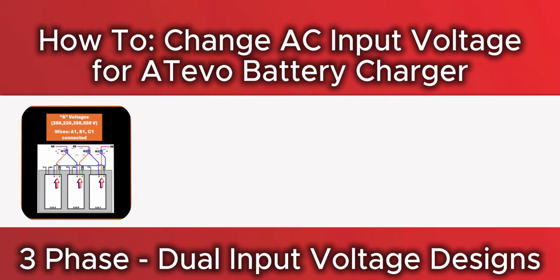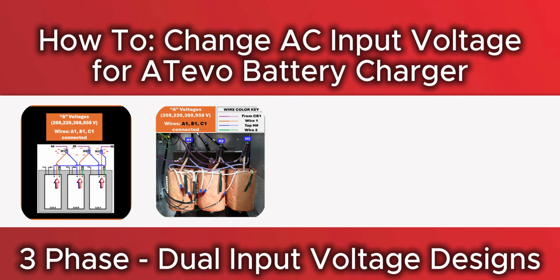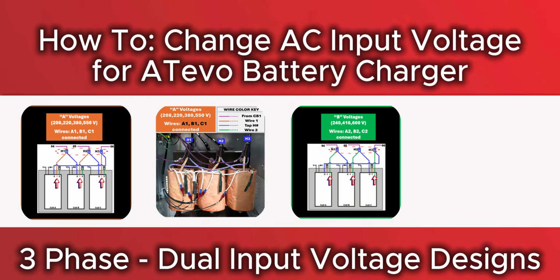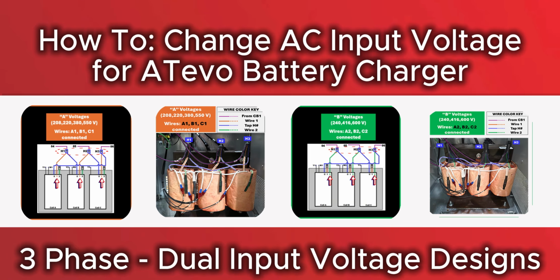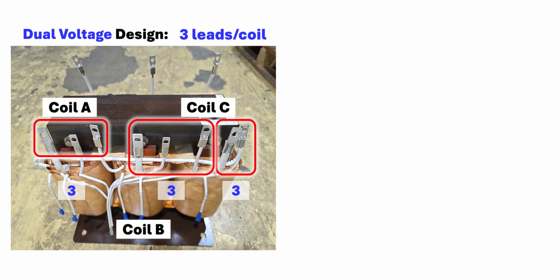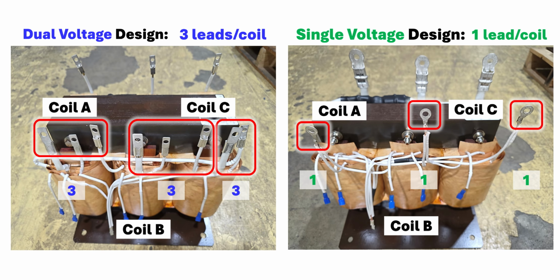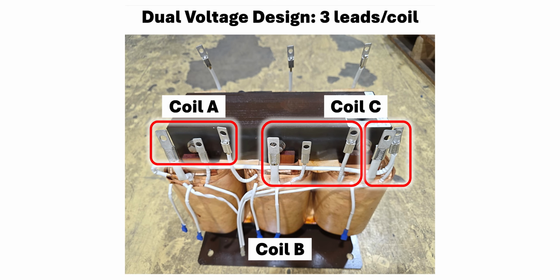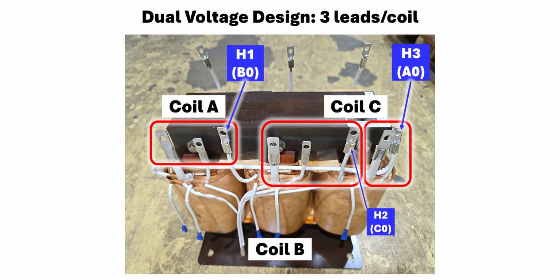Welcome! In this video, we will demonstrate how to modify the AC input voltage for a 3-phase ATevo battery charger with a dual input voltage design. Some ATevo 3-phase battery chargers feature power isolation transformers with dual voltage designs. These feature 3 leads on each transformer coil instead of a single lead per coil, as used on single voltage transformer designs. In dual voltage designs, the transformer taps H1, H2, and H3 can be rewired in the field to change the input supply voltage accepted by ATevo.